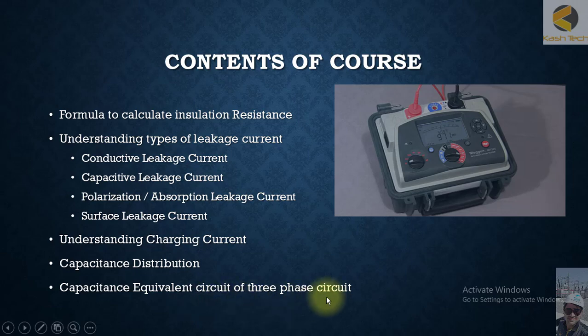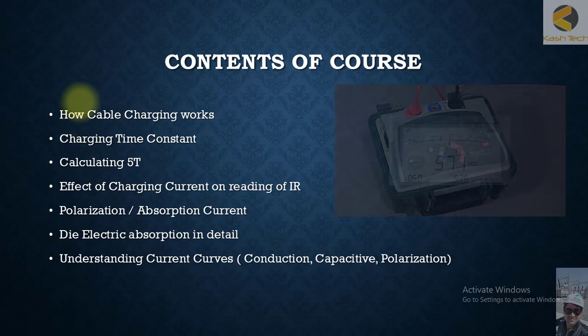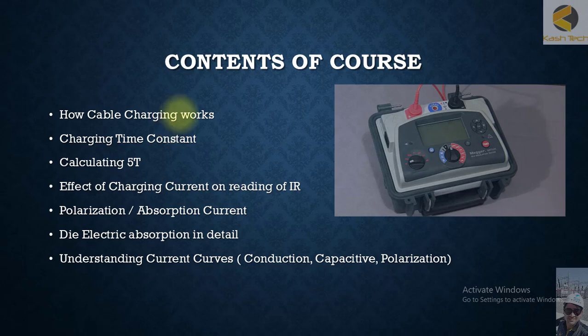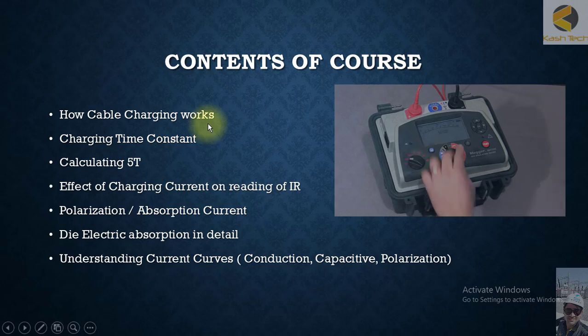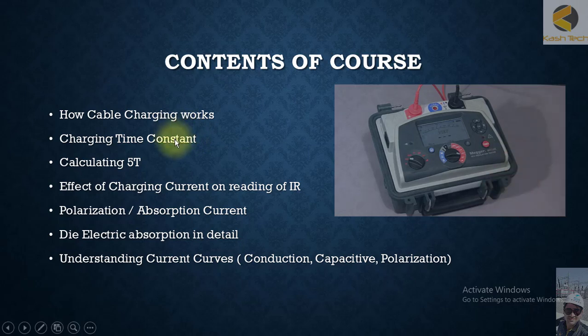Each cable has some capacitance, so we will see the capacitance equivalent circuit of a three-phase circuit and how cable charging works. We will discuss how the phenomenon of cable charging affects the Megger reading and how to eliminate this error. Since a cable is essentially an RC circuit where T = RC, we will calculate the time constant and 5T — cable charging is nearly 100% complete at five times the time constant.